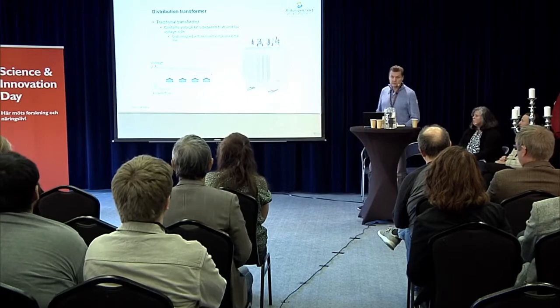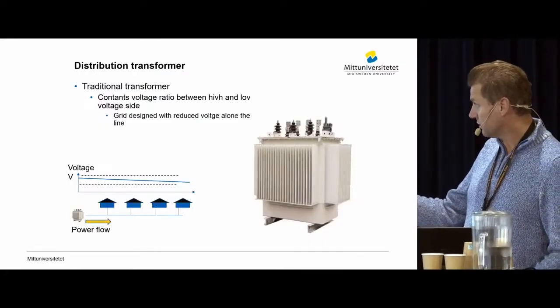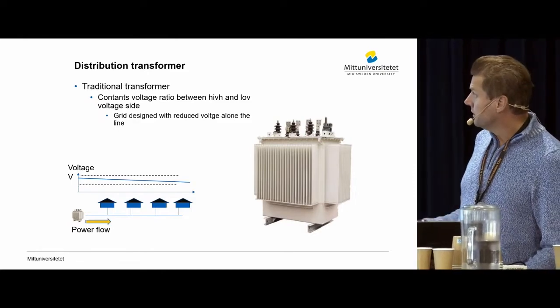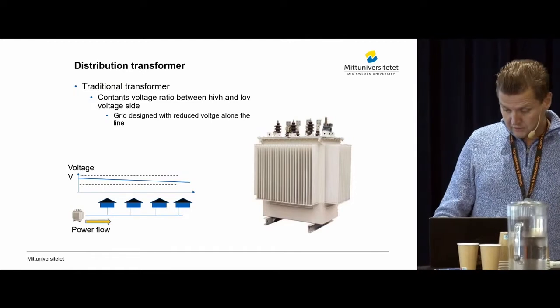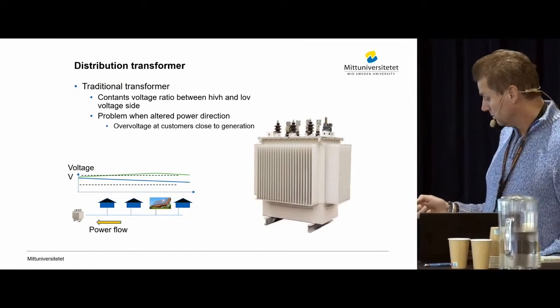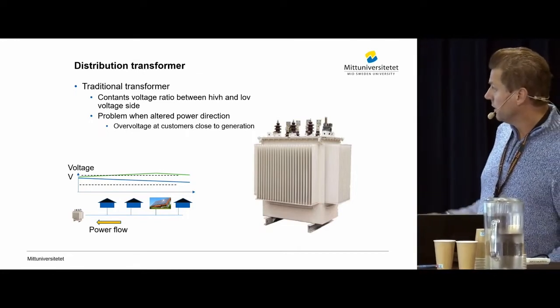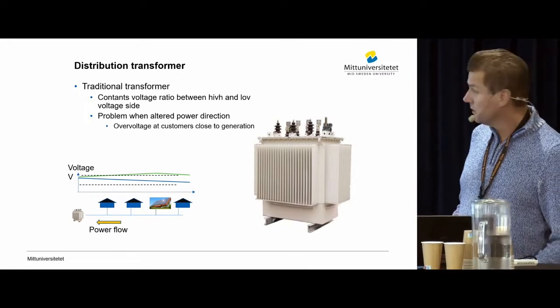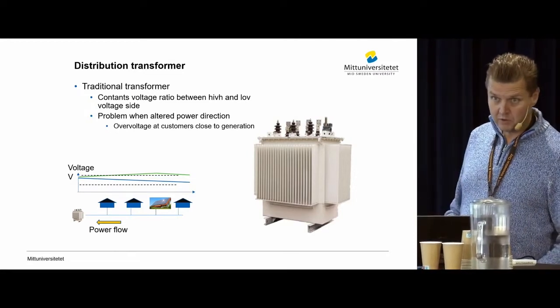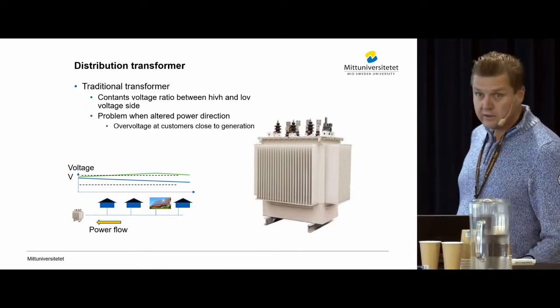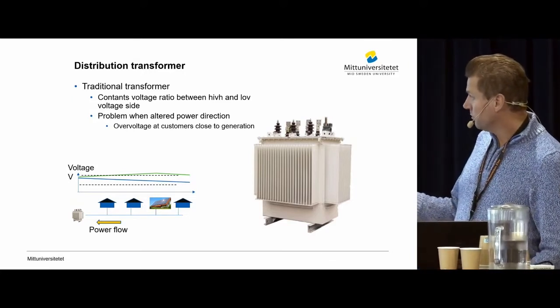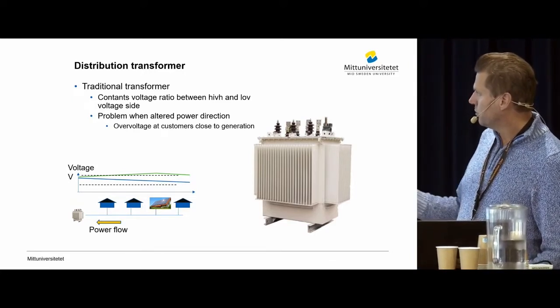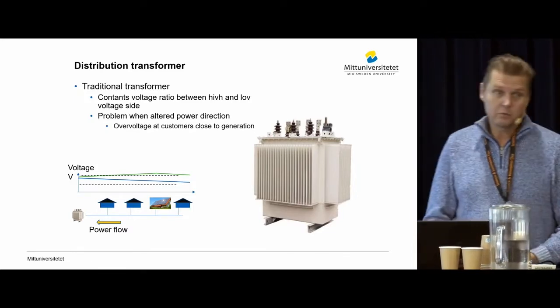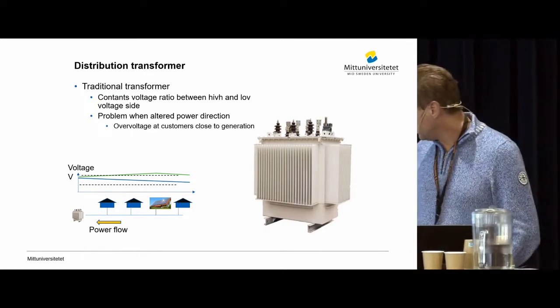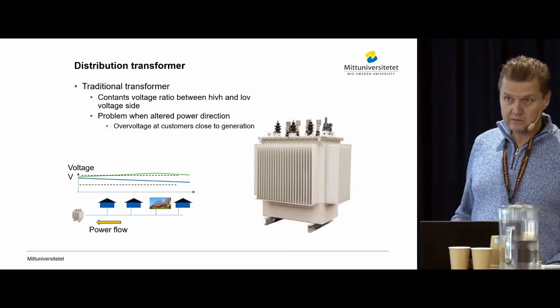One example that occurs in the normal system: it was designed so that closer to a transformer, further out on the line, the voltage is dropping, because the power direction goes from the transformer out to the grid. But nowadays, lots of customers would like to place solar power far out in the grid. A problem occurs on a sunny day in summer with low consumption: the power flow is reversed, and since the system was designed for the other direction, the voltage rises instead on the power line. Then the neighbors get very angry because their television sets are damaged and so on.